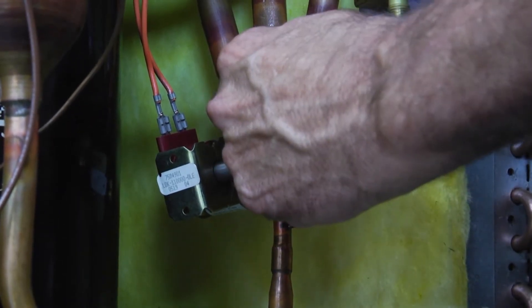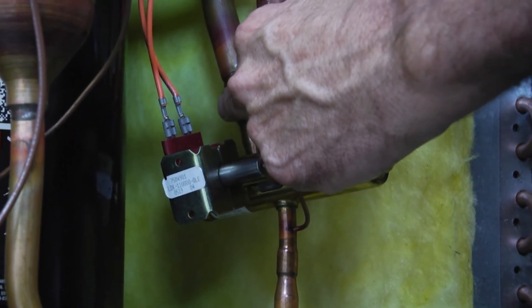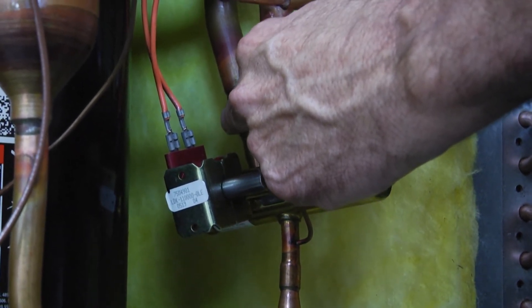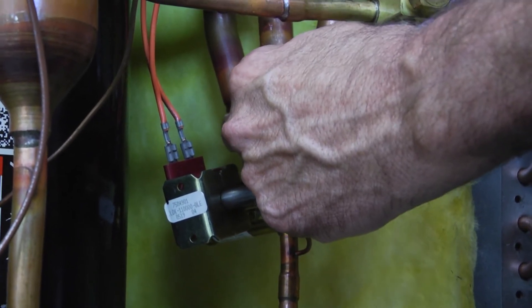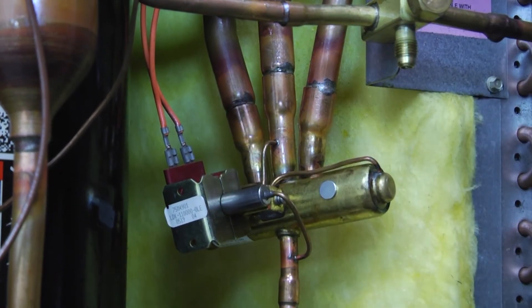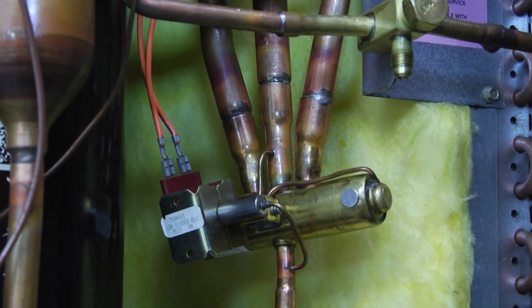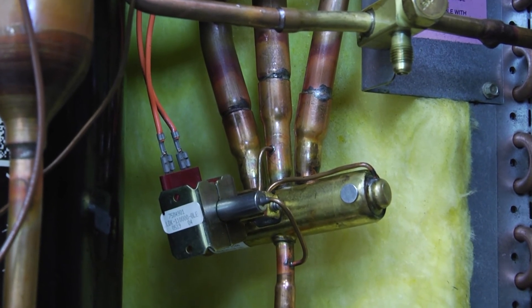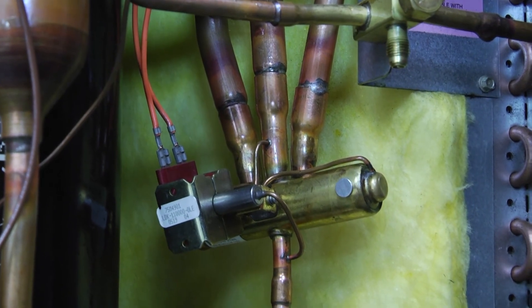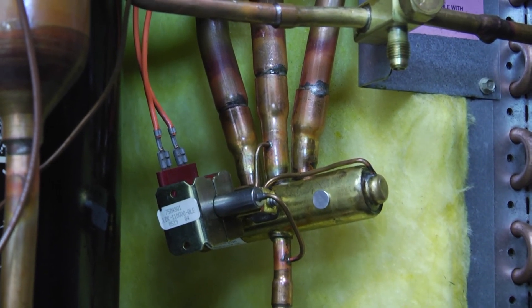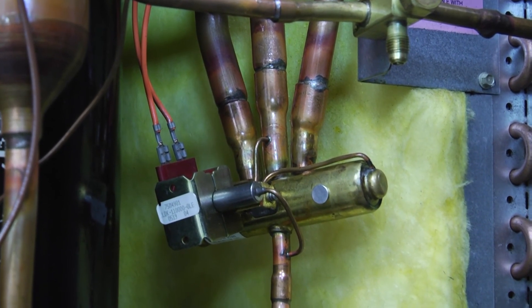So, a touch test for the two common suction ports, and then a visual test with the magnet. That way you can verify the reversing valve is either working or non-working.